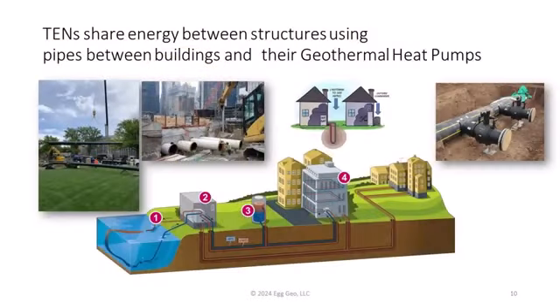This is what a thermal energy network distribution line looks like. These two taps go to a building, maybe a 300-unit apartment building, about 600 tons in capacity, and they're the beginning of what's called a decoupled secondary circuit, where water is pulled inside the building. Pumps draw water from the constantly circulating energy network into the building, they either take heat from it or put heat into it, then return it, and it keeps moving down the line — hopefully giving heat to another building or using heat from another building.